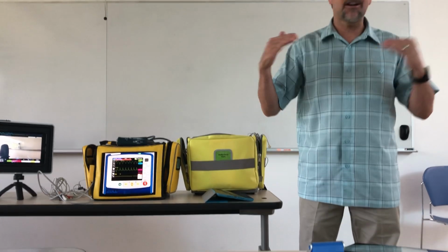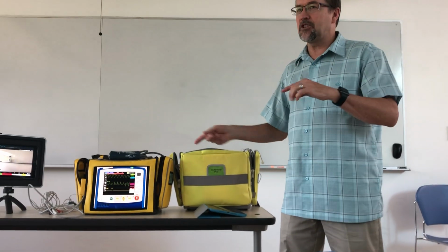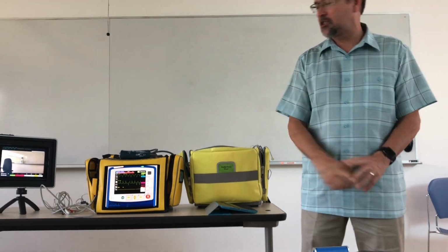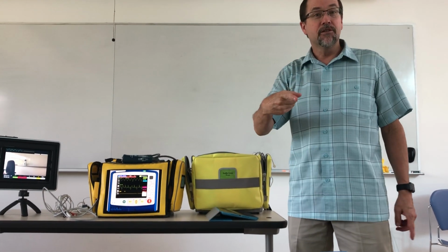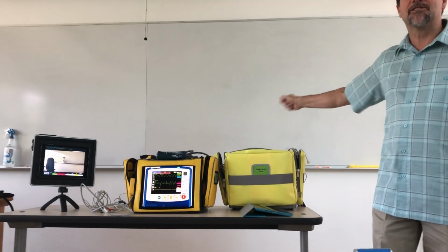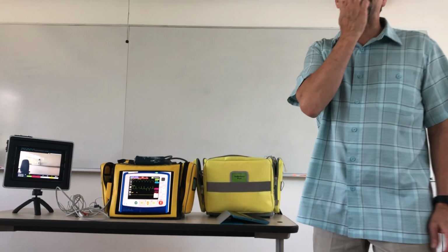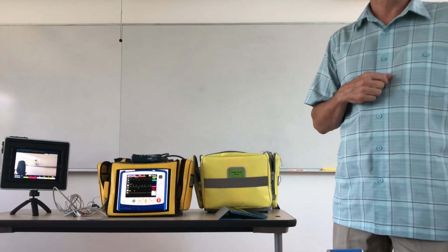We'll find out. I'm not sure if it's fine-tuned enough that when you start compressions, it switches the ECG into the CPR view. It should. One of the things that students would do is start messing with the sensor once that thing's going. They can be wiggling the sensor over here to the side, and it's going to have the same kind of look to it.